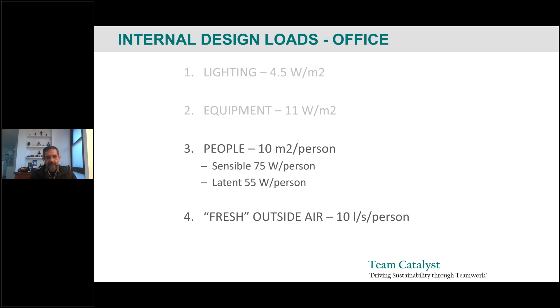You don't always have one person every 10 square meters, that's your design peak load. You need to make some assumption about how this occupancy load varies over time, so again you have some sort of schedule.